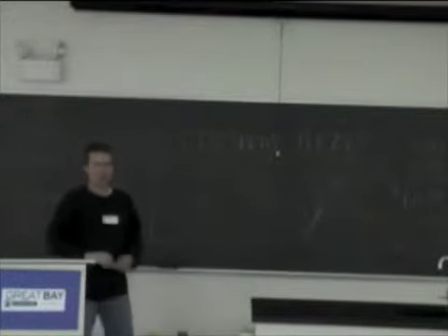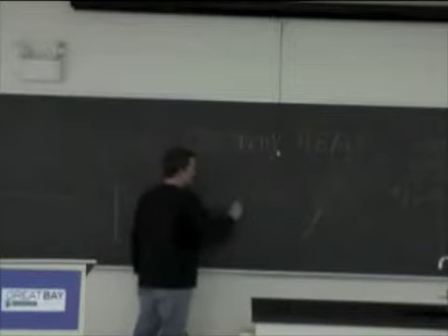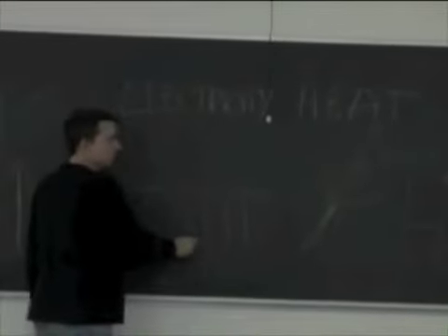I know that Nathan talked, when he was talking about doing something at this facility, a geothermal company approached him, and he said he'd be happy to hear what they could do. There's a couple of challenges with geothermal on a building this size. One is the most expensive part of a geothermal system is the wells, and so the more wells you have to drill, the more expensive it is. And this building, because of how much heat it uses, you'd be spending a lot more money drilling wells. You're better off spending that money trying to tighten up the building and get it down to the place where you can cut out some of these wells and then look at it.